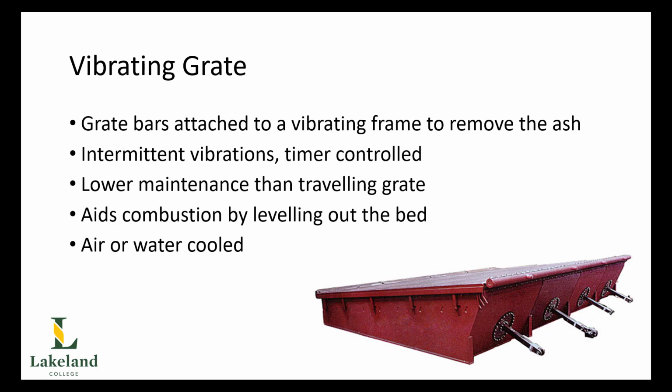Now these have much less moving parts that's going to move a lot less distance, so it will have reduced maintenance than the travelling grate. And the beauty with the vibrating grate stoker is, as it is shaken, the level of the fuel will then sort of level itself out, so we get better complete combustion. So that's a real big advantage with this. Vibrating grate stokers can either be air-cooled or water-cooled. Depends upon the arrangement of the furnace. If they are water-cooled, it means that the bottom of the grate has water tubes running through it to keep it cool, thereby increasing our heat transfer surface area.